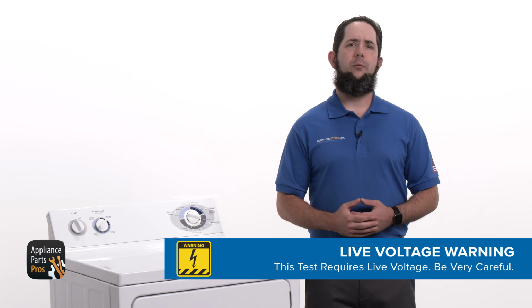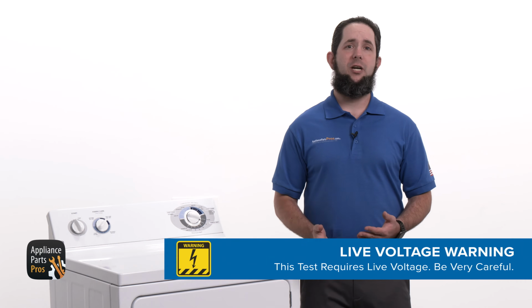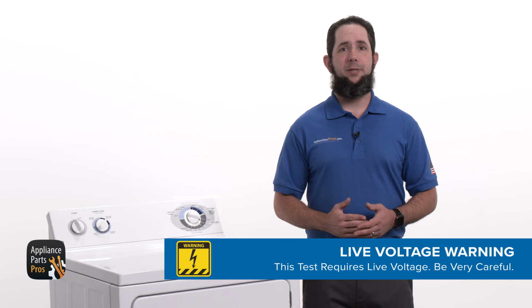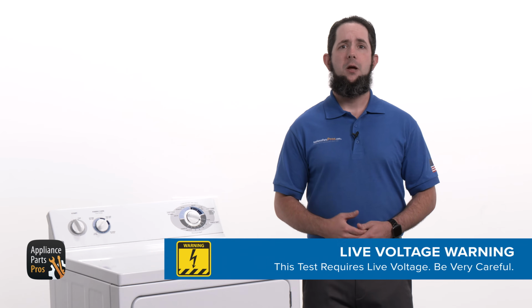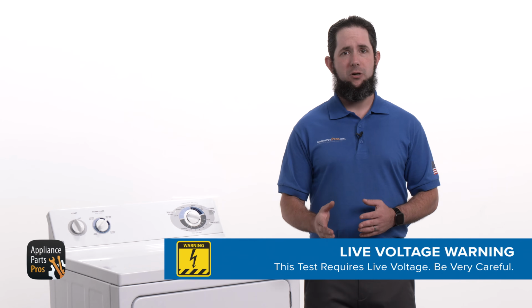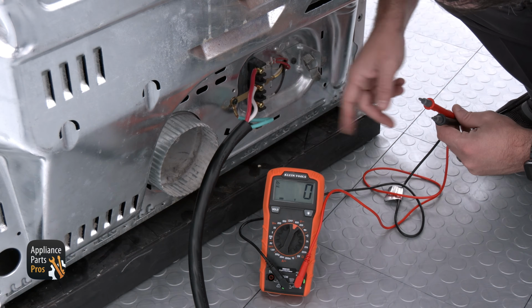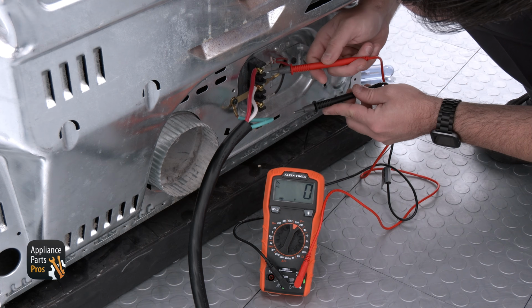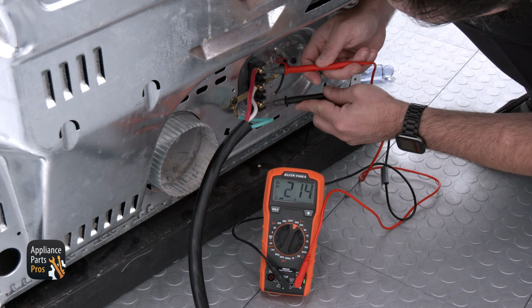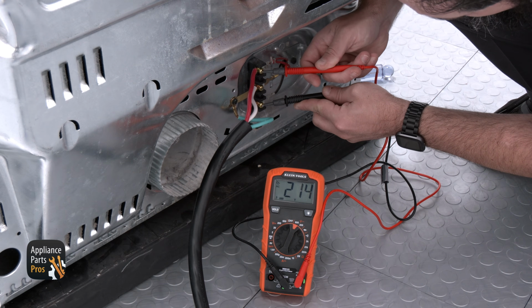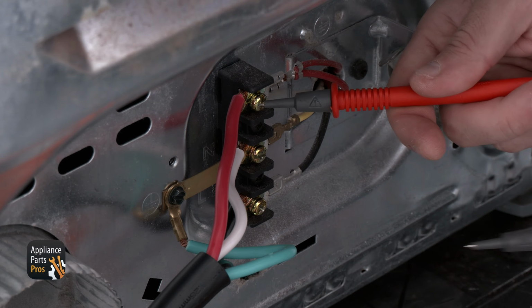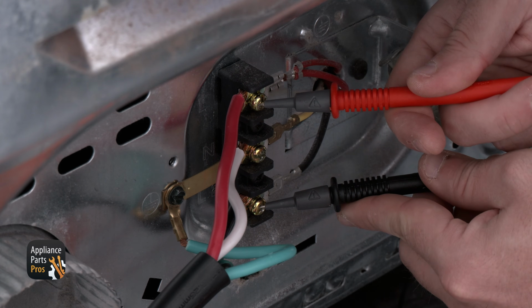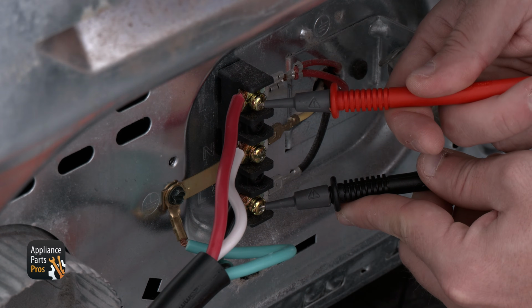Always take extreme care when checking live voltage so you can protect yourself from electric shock, which has the potential to cause serious injuries. Please don't ever test live voltage if you're uncomfortable using a multimeter. Before we really dig in, we're going to grab our multimeter and check to make sure we have 240 volts AC at the terminal block of our dryer. The terminal block is at the bottom of the back of the dryer and might have a cover that needs to be removed to access it.